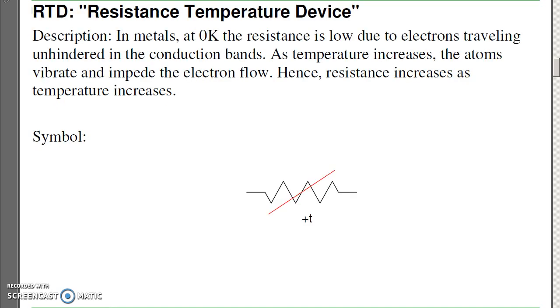Starting out, a resistive temperature device, or RTD. RTDs are made of metal. At zero degrees Kelvin, the resistance is very, very low because the electrons are traveling unhindered in the conduction bands. As temperatures increase, the atoms start moving around, impeding the flow of the electrons. Hence the resistance goes up with temperature.